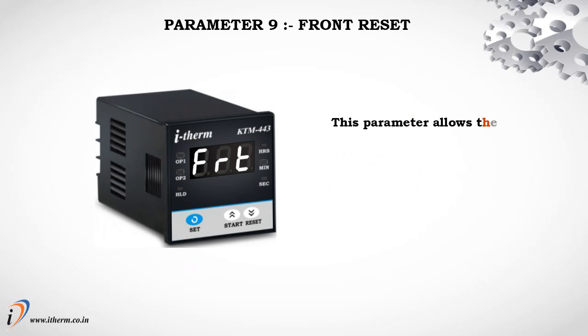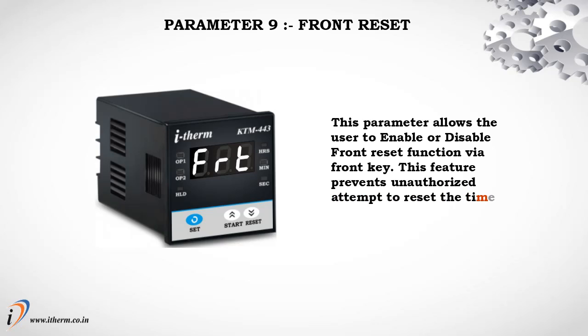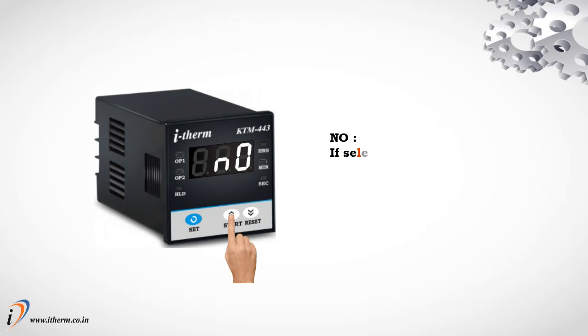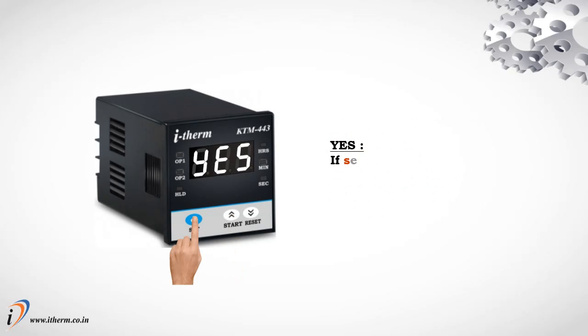Parameter 9: Front reset. This parameter allows the user to enable or disable the front reset function via the front key. This feature prevents unauthorized attempts to reset the timer during run mode. If selected No, the timer cannot be reset through the front panel. If selected Yes, the timer can be reset through the front panel.